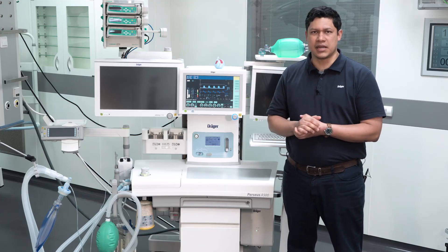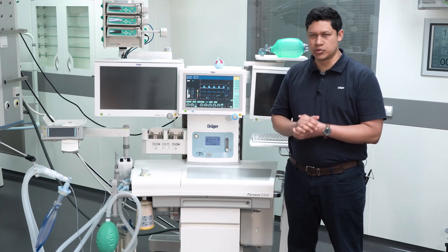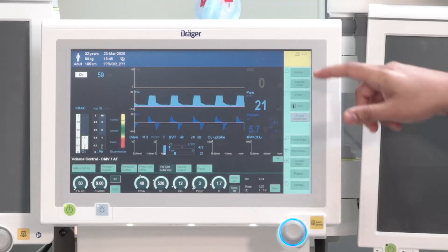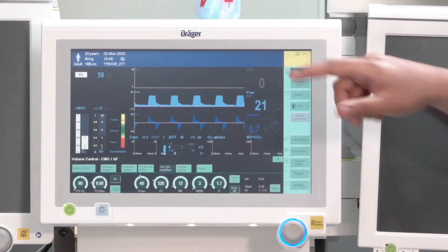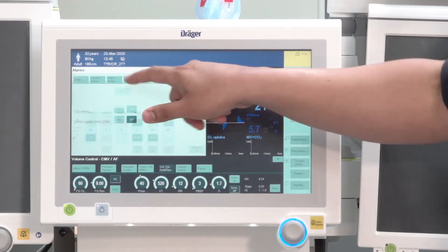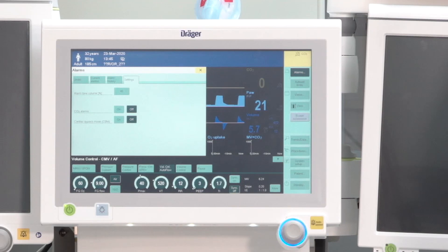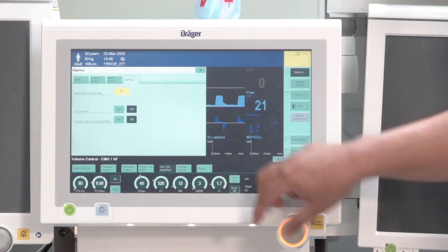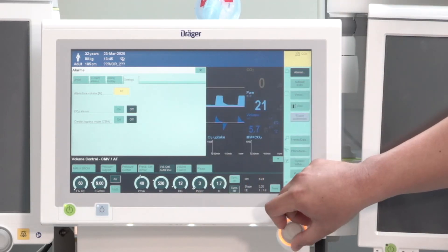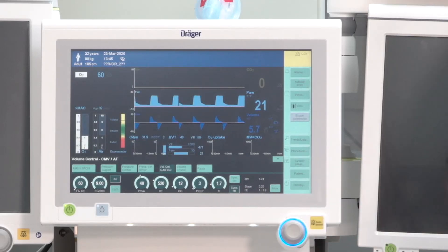Always verify that the level of volume is set to the maximum. To do so, go to the alarm button, then go to the settings tab, and set the maximum level for the alarm. Don't forget to always confirm using the rotary knob.